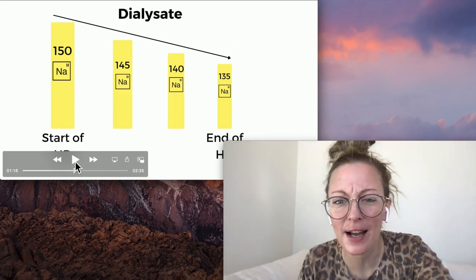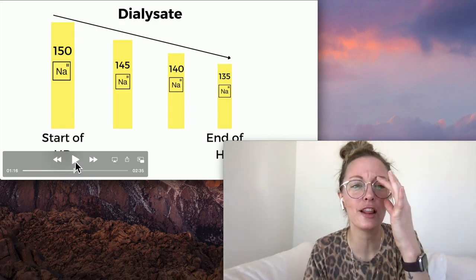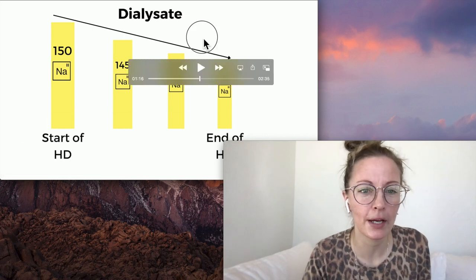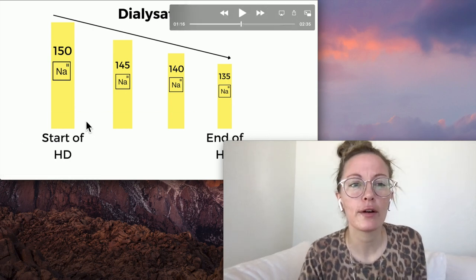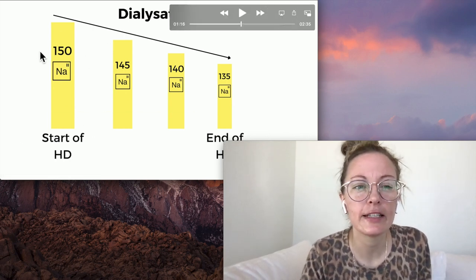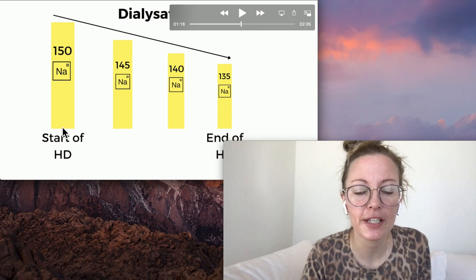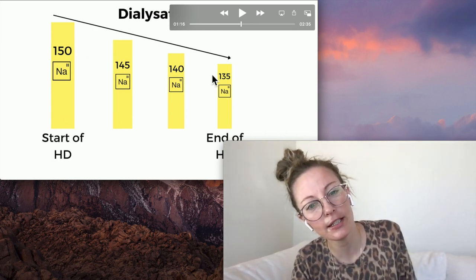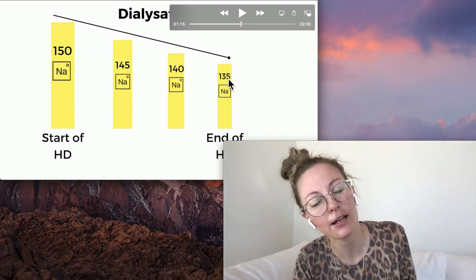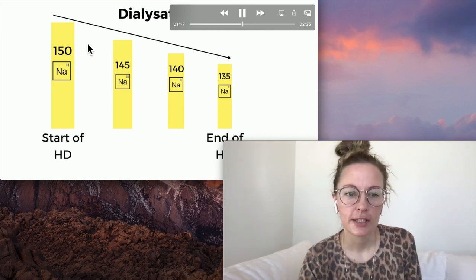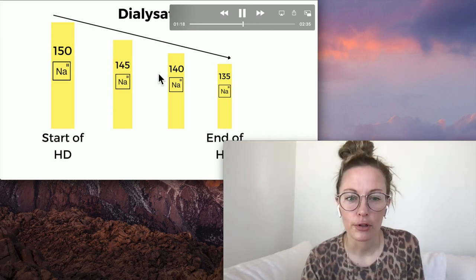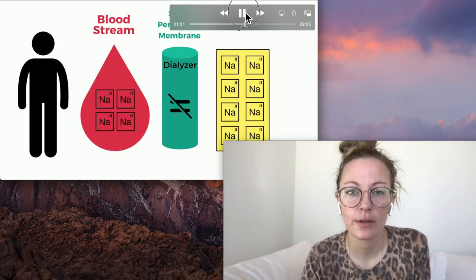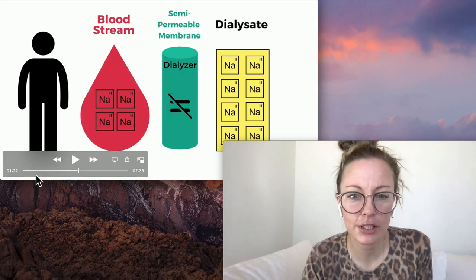Of course I have a visual for you. This is what it looks like — it might even be what your screen looks like. At the start of dialysis we set the conductivity, the sodium, at 150. And at the end of dialysis we progressively decrease the conductivity down to 135 — stagger it down. A progressive profile of sodium.